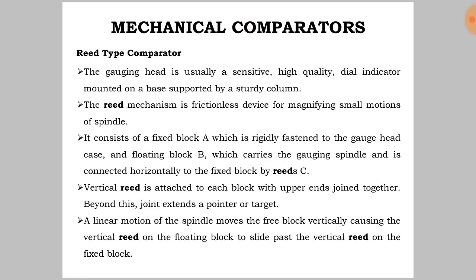The gauging head is usually a sensitive, high quality dial indicator mounted on a base supported by a sturdy column. The reed mechanism is a frictionless device for magnifying small motions of the spindle. It consists of a fixed block A, which is rigidly fastened to the gauge head case, and a floating block B, which carries the gauging spindle and is connected horizontally to the fixed block by reeds C. A vertical reed is attached to each block with the upper ends joined together. A linear motion of the spindle moves the free block vertically, causing the vertical reed on the floating block to slide past the vertical reed on the fixed block.